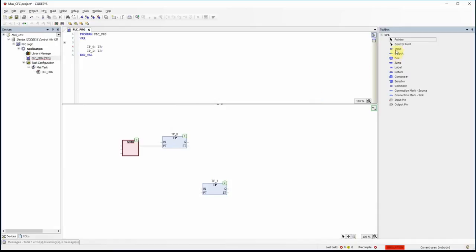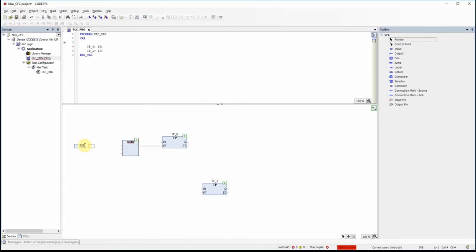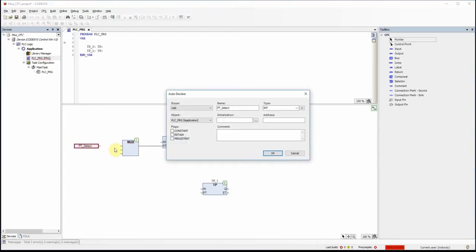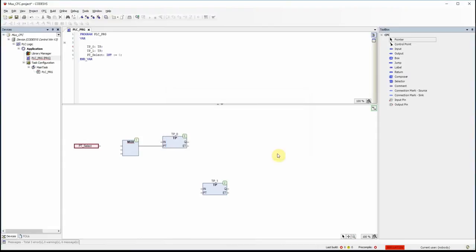This means I need an integer input here. I will call it pt_select — selecting the preset time. By default its type is integer; I can initialize it with 0 and press OK. You can see it appears in the variable declaration area, and now I can connect it to the first input of the multiplexer.